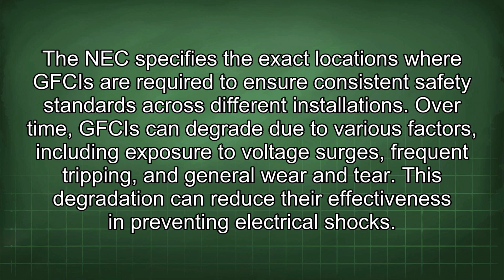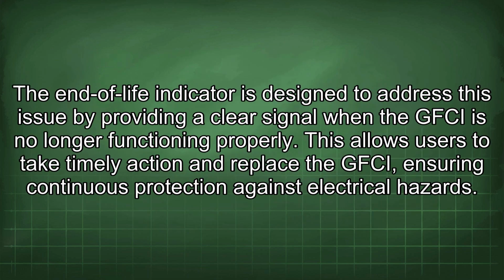Over time, GFCIs can degrade due to various factors, including exposure to voltage surges, frequent tripping, and general wear and tear. This degradation can reduce their effectiveness in preventing electrical shocks. The end-of-life indicator is designed to address this issue by providing a clear signal when the GFCI is no longer functioning properly. This allows users to take timely action and replace the GFCI, ensuring continuous protection against electrical hazards.